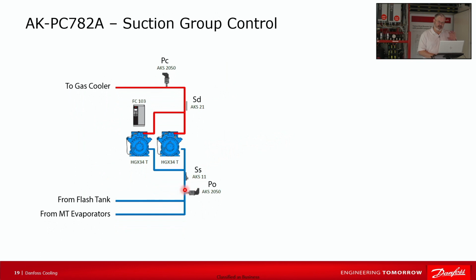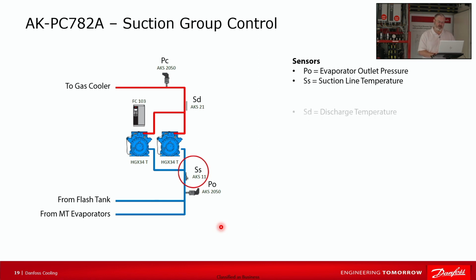So we're just going to take a caption of the 4 areas we identified. Coming into our medium temp suction, we've got return from the flash tank, where we're venting off the flash tank, as well as our suction line return from medium temp evaporators. The sensors that we need for that are going to be the evaporator outlet pressure. We've got a sensor on the suction line so we can monitor superheat, so we can do something if we realize we're getting liquid back.